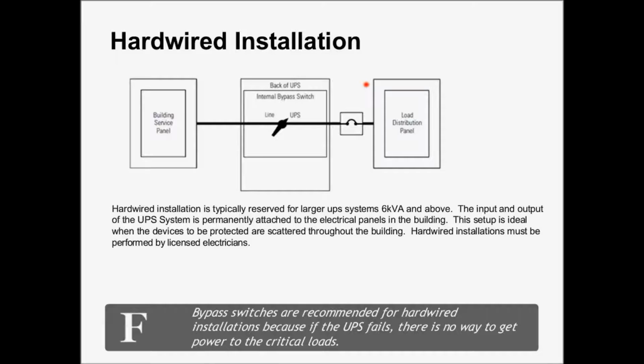Now, the other way that you can install a UPS is a hardwired installation. Essentially, hardwired just means it's wired directly into the building. The way it's generally done is you have an input panel to the UPS. A lot of times it's called a building service panel. And this wires into the UPS. And then on the UPS, you have a bypass switch. And then you come out of the UPS to what's called a load distribution panel or a critical load panel. Normally this is done with UPS systems that are 6 kVA and above. Sometimes it's done with smaller ones in controls applications, but normally it's for 6 kVA and above.